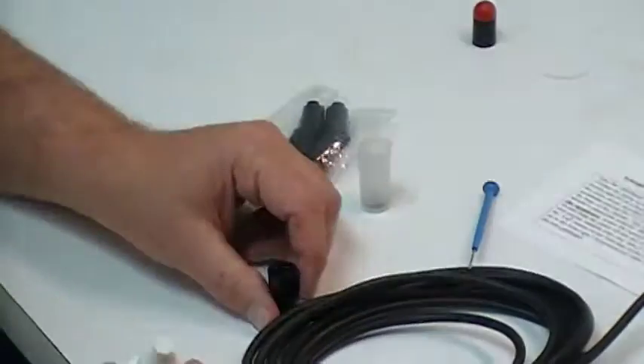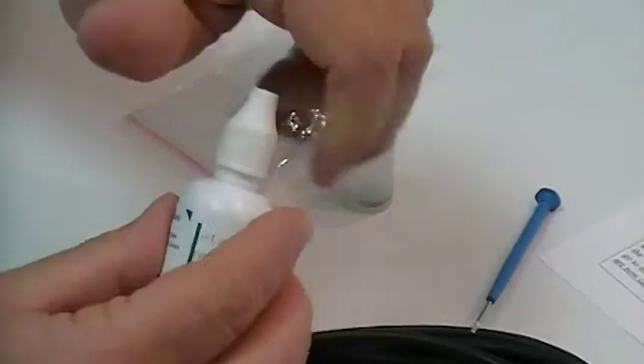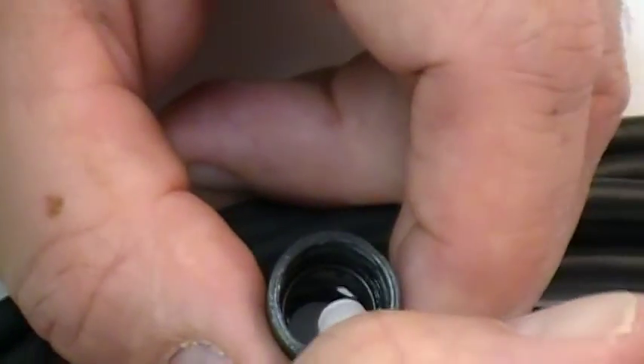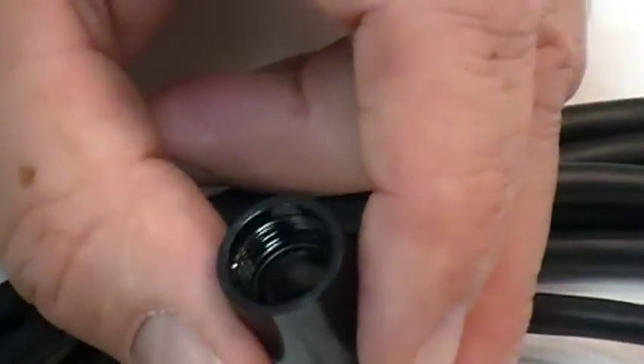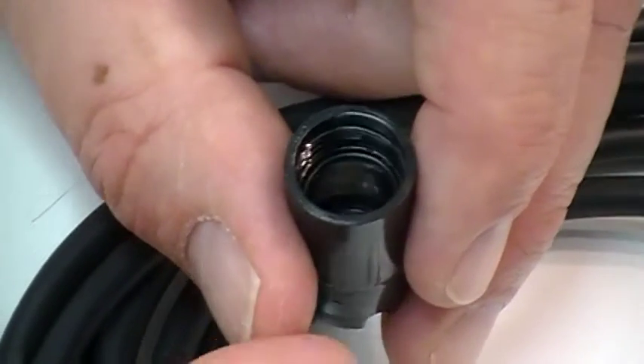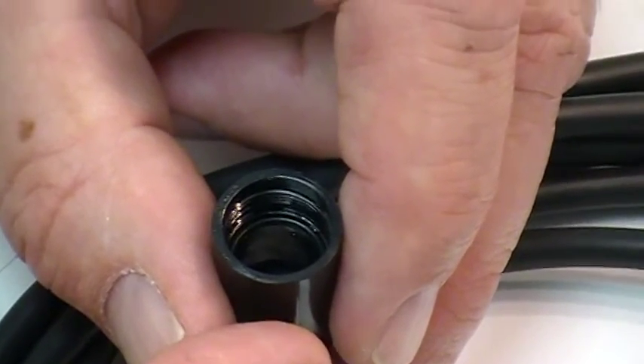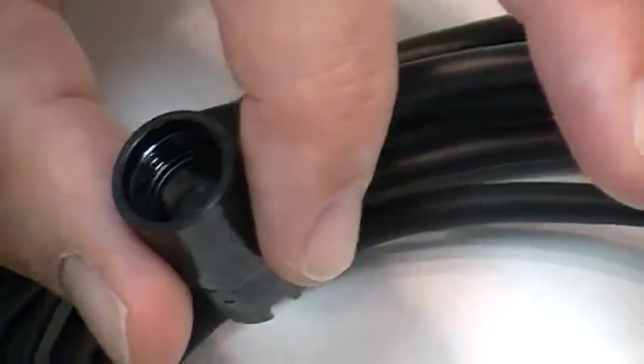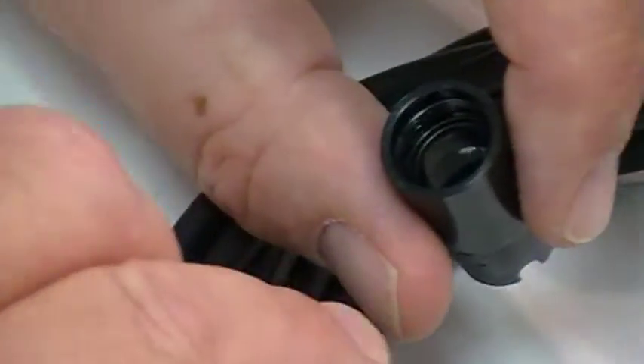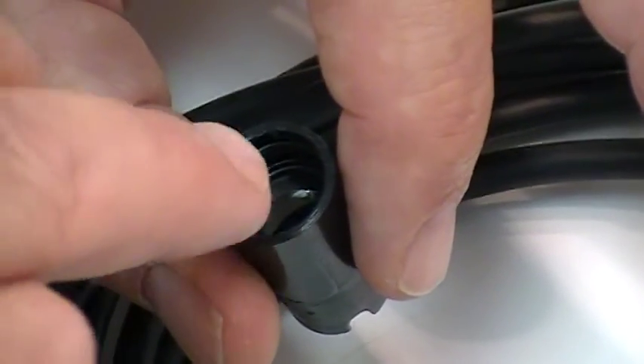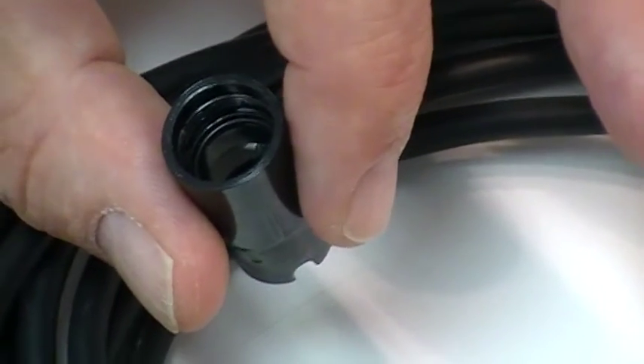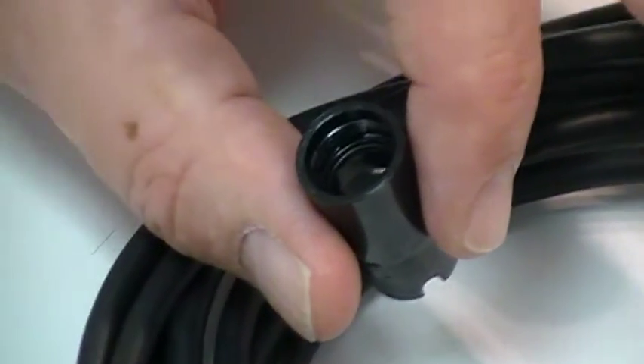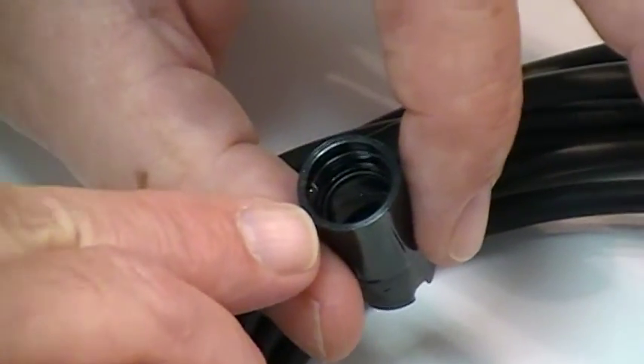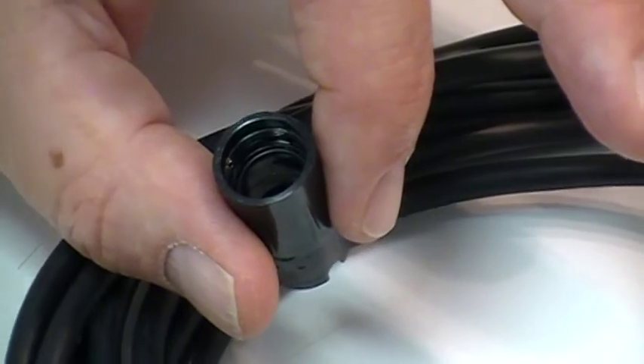When you have that done, you want to take your electrolyte solution and very gently, do not squirt, but very gently load your membrane up to the O-ring that you just put in. When you've got the electrolyte just short of the O-ring in your membrane, you want to look down through the membrane onto a white surface and look for any air bubbles that are inside the liquid electrolyte. This is where any calibration procedure will fall apart, because it must not have any air bubbles inside this membrane before it's installed onto the end of your probe.